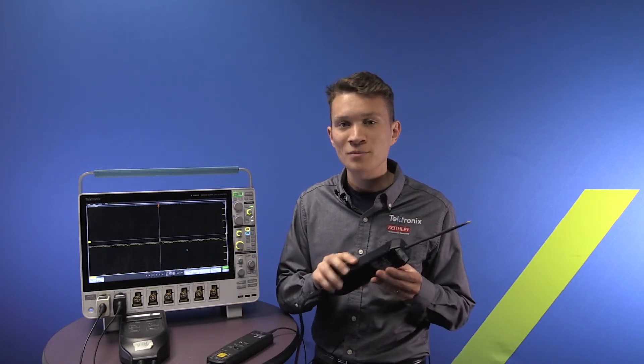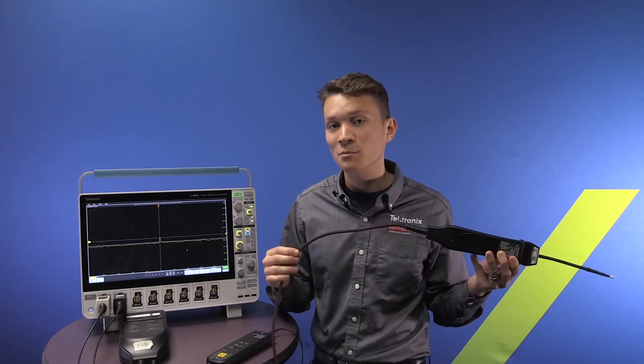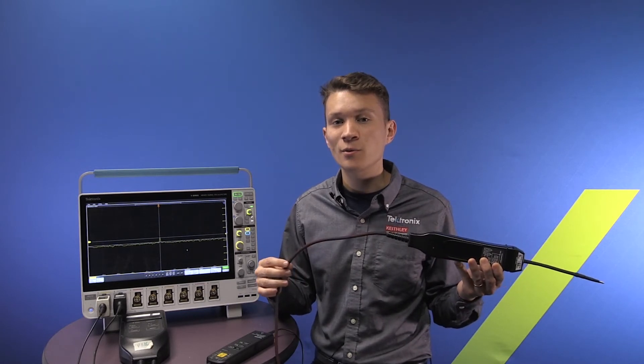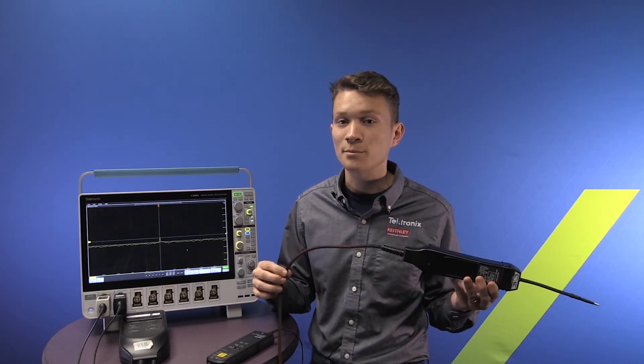To improve this design, Tektronix engineers invented an isolated probe called IsoVu. It's completely powered over fiber and it also sends the analog waveform back to the scope using fiber optics.